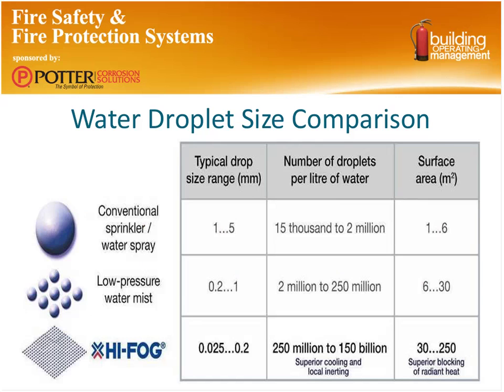So what it really boils down to is water droplet size. A typical sprinkler system has a pretty good sized droplet in the 1 to 5 millimeter range. When we get into water mist, we actually break that into two categories. There's what's called low pressure water mist, and that's where we have kind of a mid-sized droplet in that 0.2 to 1 millimeter range, so still a pretty good sized drop. Or we have what are called the high pressure water mists, and the high pressure water mists actually are in your 0.025 to 0.2 millimeter range. So pretty small droplet, and we'll see the benefits of that small droplet here in a minute.